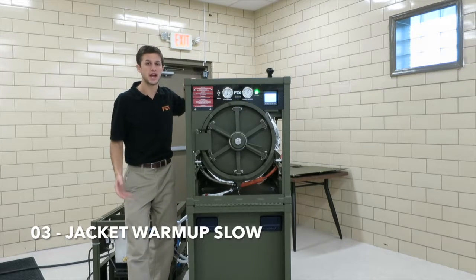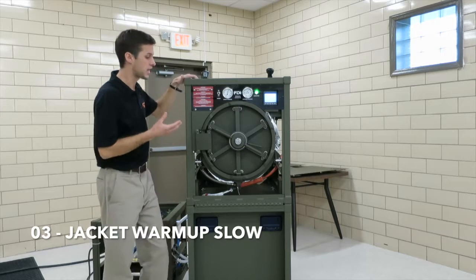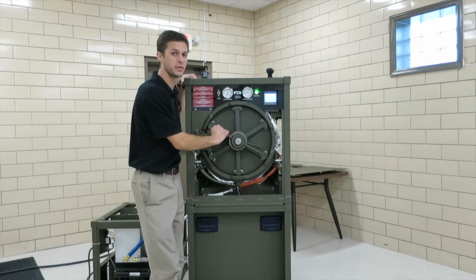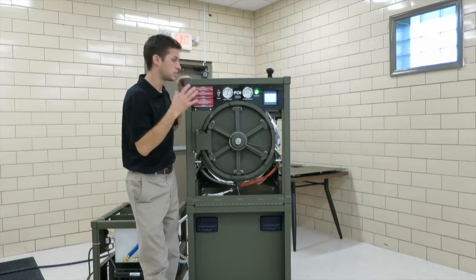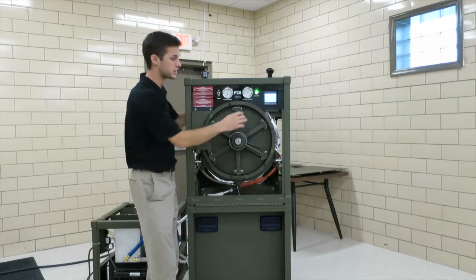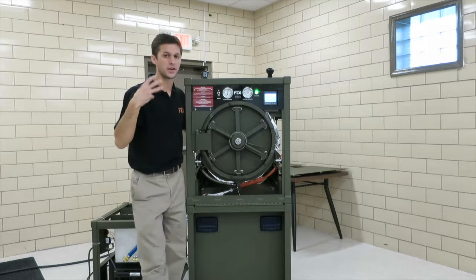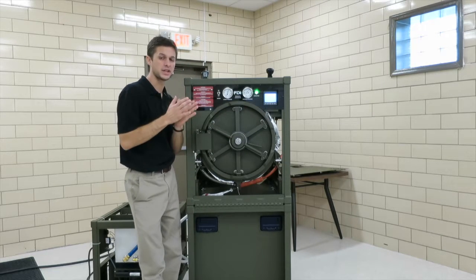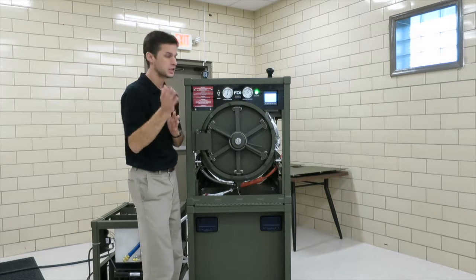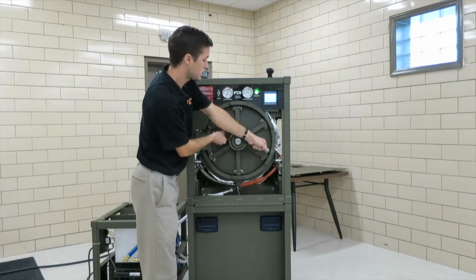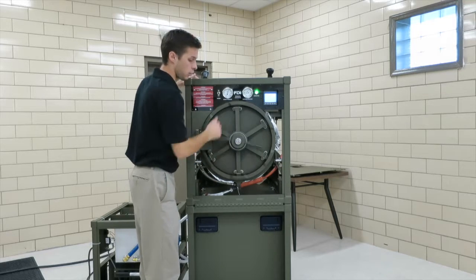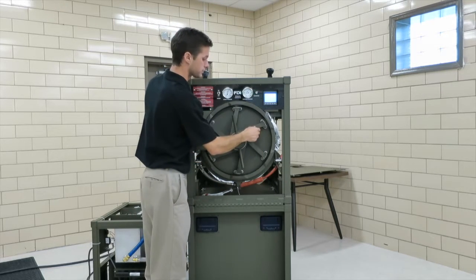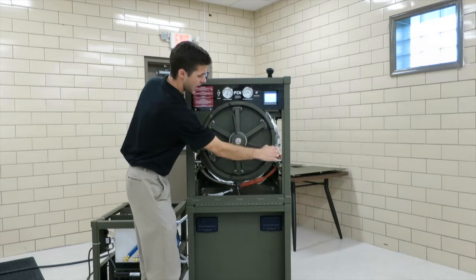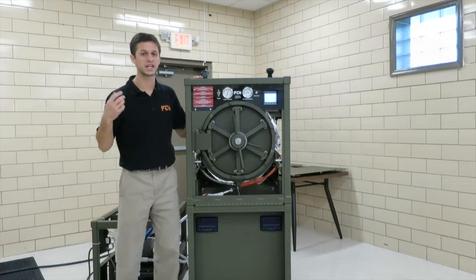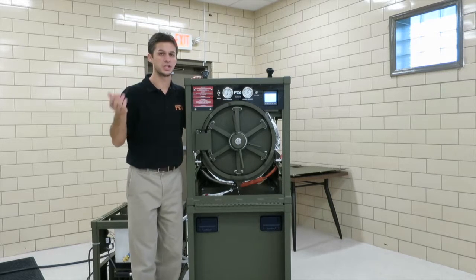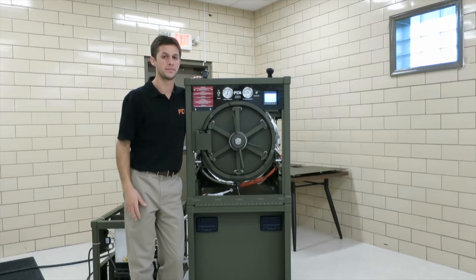03 is a jacket warm-up slow alarm. This is when we first fire this up in the morning. There are watchdog timers, and this is true for most of the alarms, that run in this PLC and are constantly checking to make sure everything is taking a normal amount of time. The jacket is where the water is boiling and heating up. It's where the heaters are, in a gap around the chamber. If that's taking more time than normal, you will get a jacket warm-up slow 03 alarm.